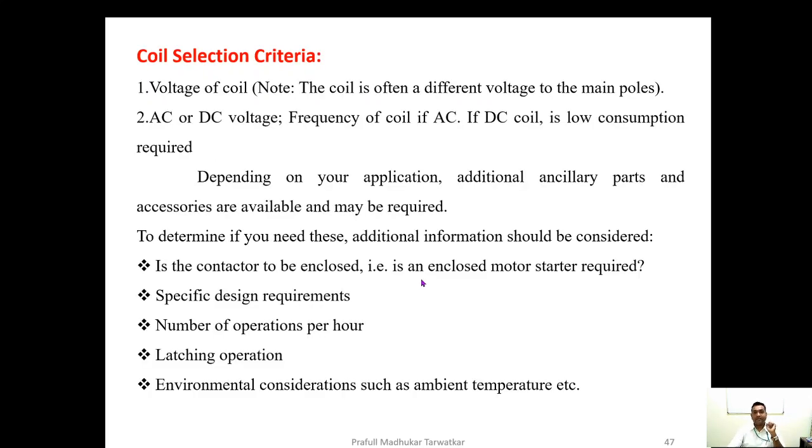Then coil. Now this is again important. The first thing is voltage of the coil, because ultimately there are contactors which are available depending on the coil voltage, 110 volt AC, 220 volt AC or 400 volt AC. So this is how the corresponding coil voltage is taken into consideration for selecting a contactor.